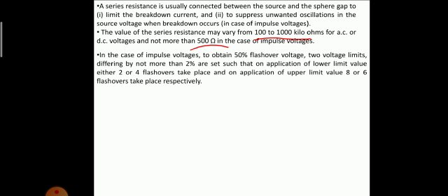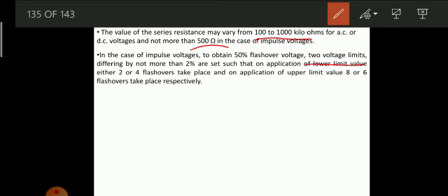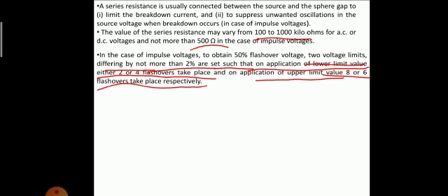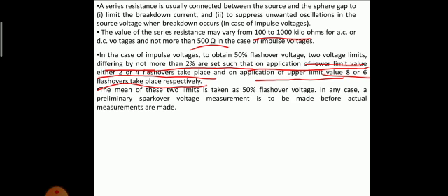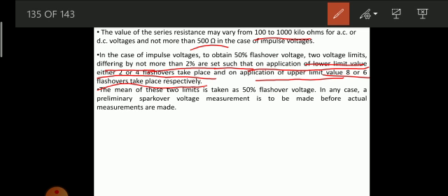Now in case of impulse voltages, to obtain the 50% flashover voltage, two voltage limits differing by not more than 2% are set, such that on application of the lower limit value either 2 or 4 flashovers take place, and on application of the upper limit value 8 or 6 flashovers take place. When you want to measure the impulse voltages, we do this type of testing. Then what we do, we take the average. The mean of these two limits is taken as the 50% flashover voltage.